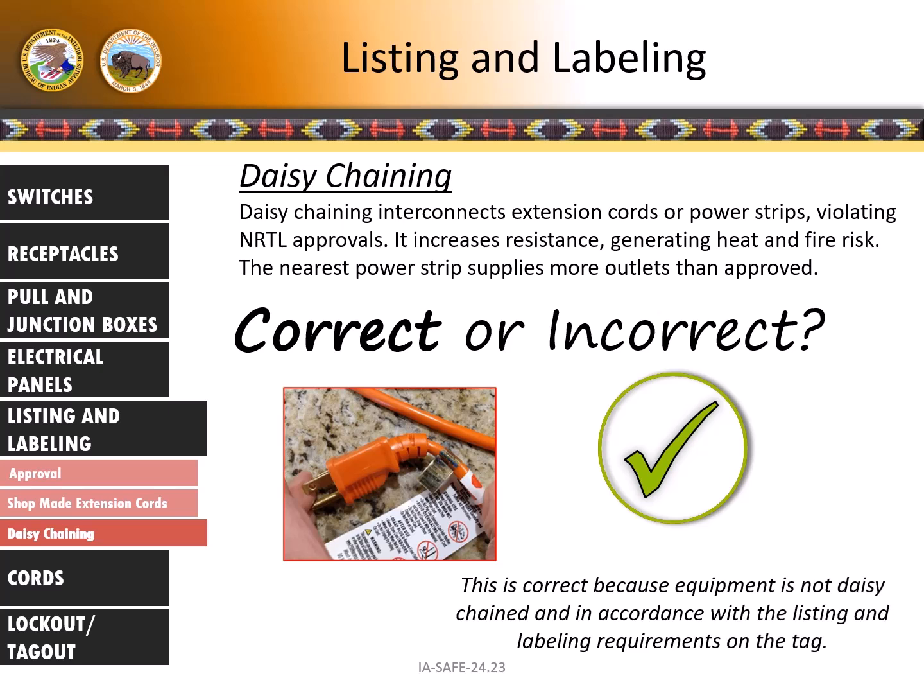This is correct because equipment is not daisy chained and in accordance with the listing and labeling requirements on the tag.